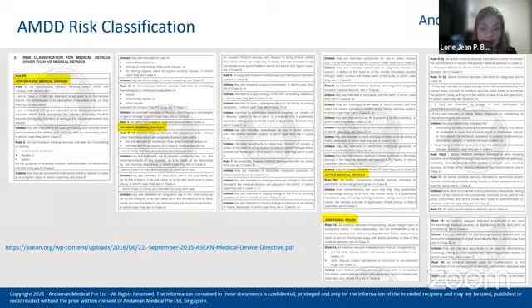The third one is the active medical devices covering rules 9 to 12. These are the medical devices whose operation depends on a source of electrical energy or any source of power other than that directly generated by the human body or gravity, and which acts by converting this energy. Examples are MRI, ultrasound, electronic thermometer, and dialysis machine. The last one is the additional rules, which cover rules 13 to 16. Examples of this are drug-eluting stents, medical device disinfectants, condoms, and IUD. For full details of the risk classification rules, you may refer to the link shown in this slide on the lower left side. So next slide, please.